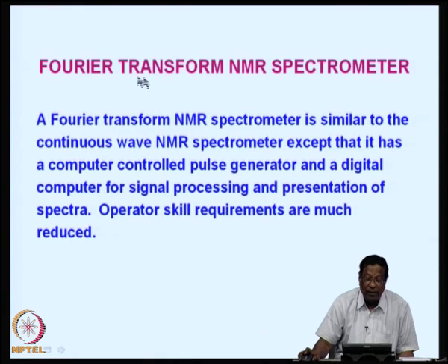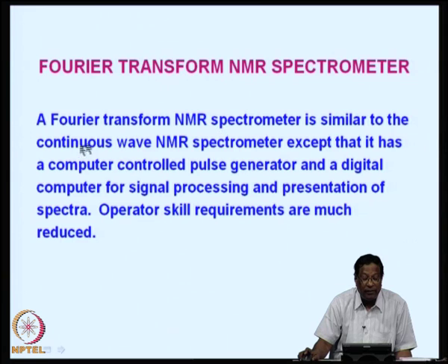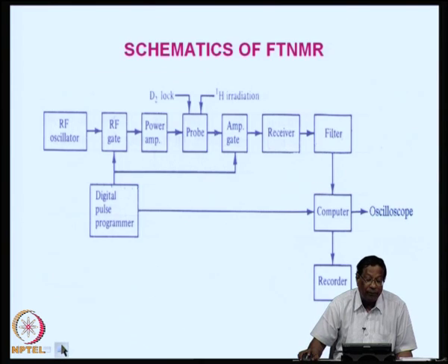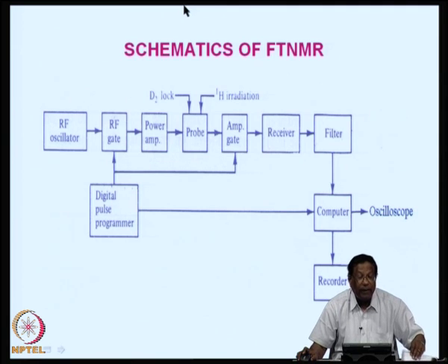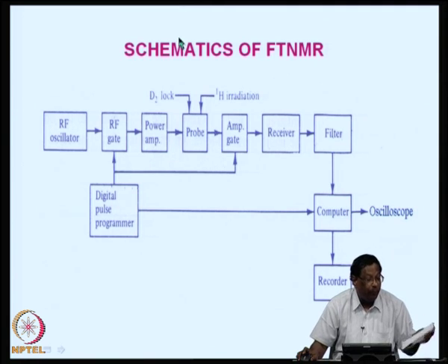So, FT NMR is similar to the continuous wave NMR, except that it has a computer controlled pulse generator and a digital computer for signal processing and presentation of the spectra. So, operator skill requirements are much reduced in FT-NMR.